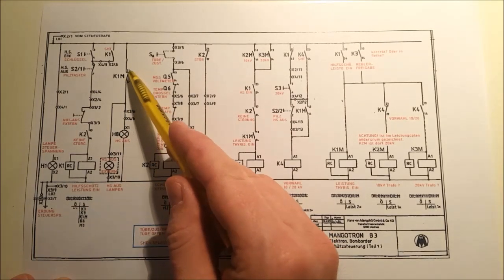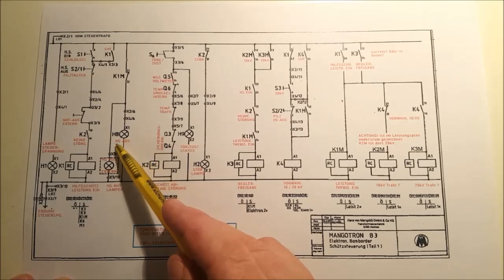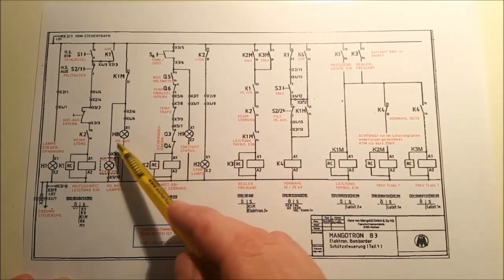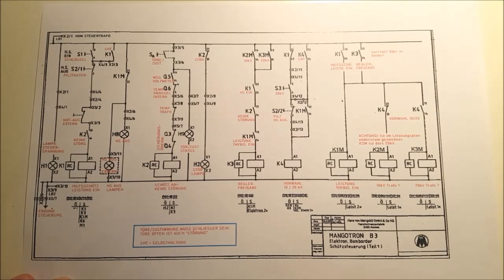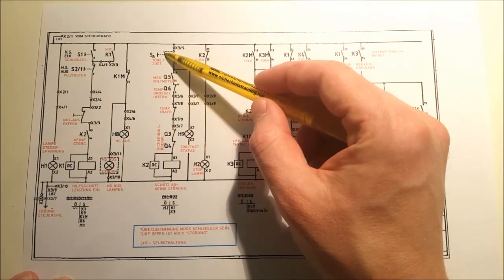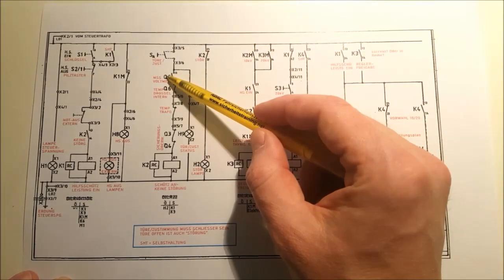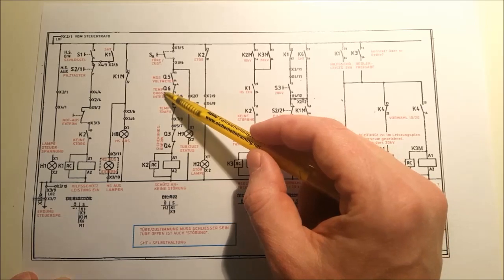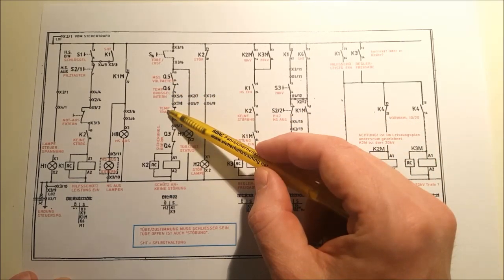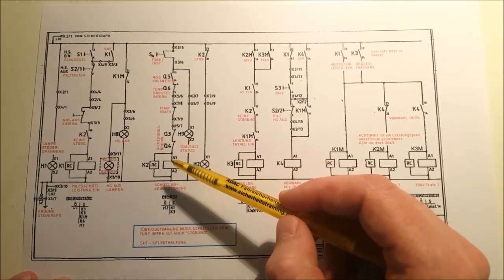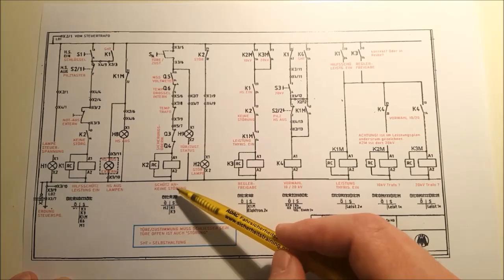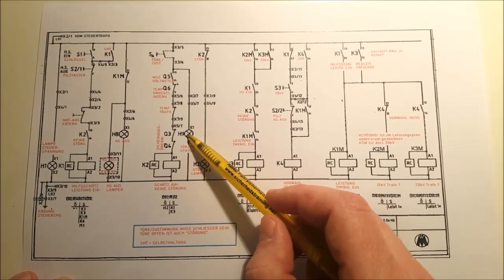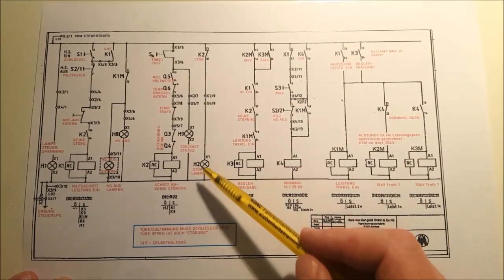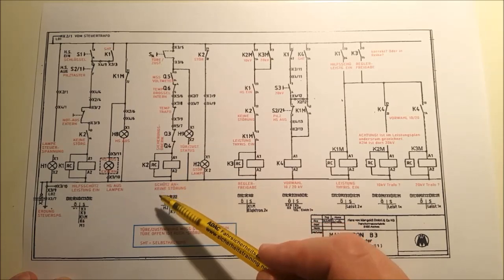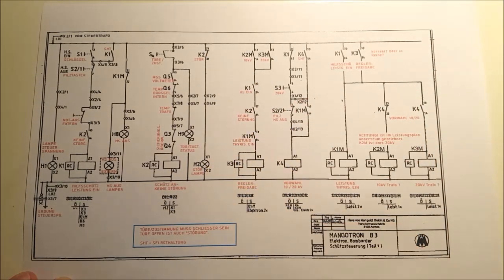As long as the K1M was off, current was going through here and lighting up these lamps that say high voltage off. So as soon as this pulls in, high voltage off lamps go out. Then this contactor says no error, so the conditions are a door switch or a foot switch or whatever is closed. Then the breaker for the voltmeter is okay, the temperature switch in the choke is okay, the temperature switch in the transformer is okay, and both the special fuses are okay. Then this contactor pulls in and says we have no error. This lamp gives the status of the door or the foot switch, and this is the error lamp. So as soon as this contactor no error turns on, this contact opens and the error lamp goes off.